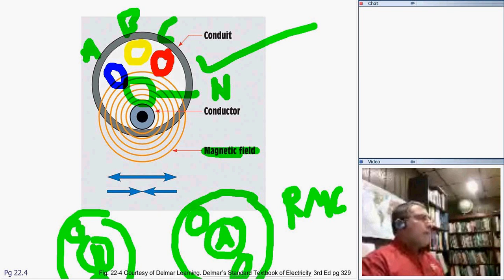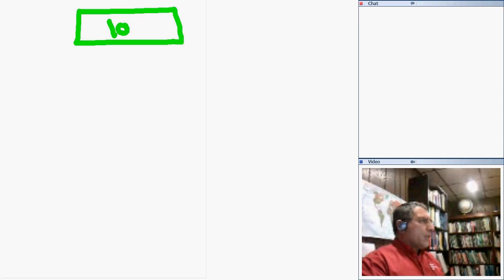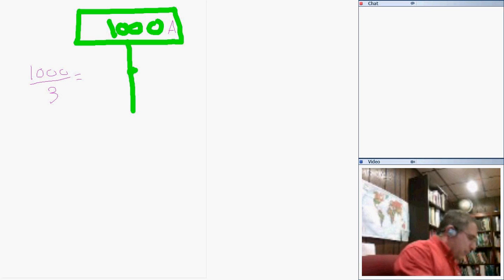Any question, guys, about paralleling? Let's take a quick question. Let's just suppose that you guys have a 1000 amp switchboard, and I need to parallel the conductors for that switchboard, right? That's typical, parallel the conductors. When I want to size the conductor for that baby, remember, it's 1000 amp. What I would do, guys, is take the 1000 and divide by 3, because you want to be in the 300 range.